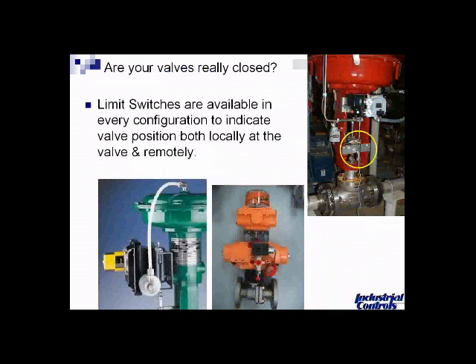But limit switches, if you look at these packages here, inside these enclosures there typically are 2 micro switches that will send a signal back for a full open or full closed position. And the other nice thing about these is they have visual indicators on top that will tell you if the valve is open or closed. So these limit switches are available in just about every configuration you can imagine. Again, they'll give you indication locally at the valve and also remotely back in the control room.